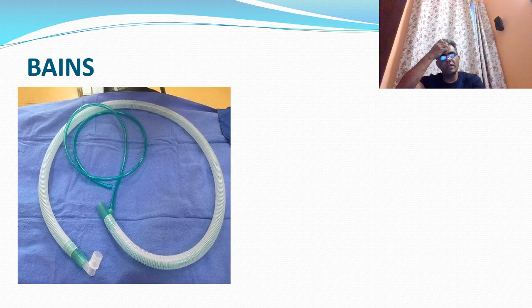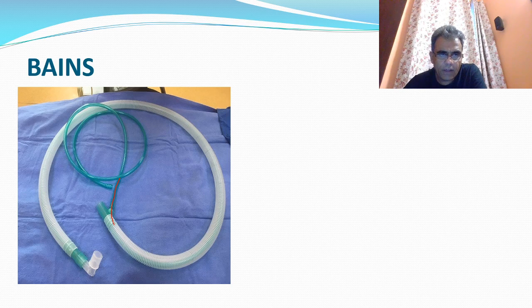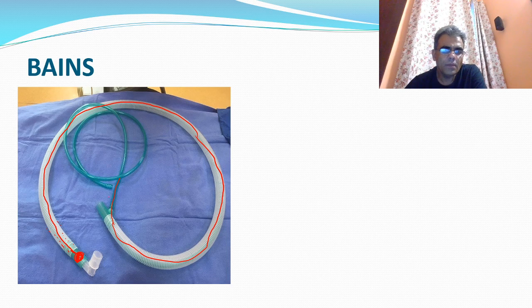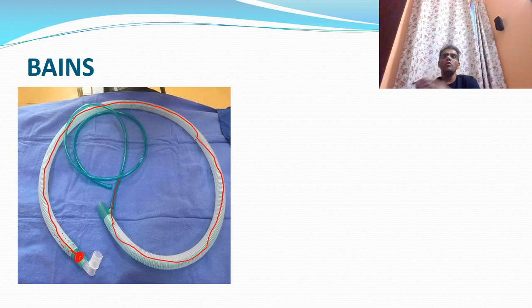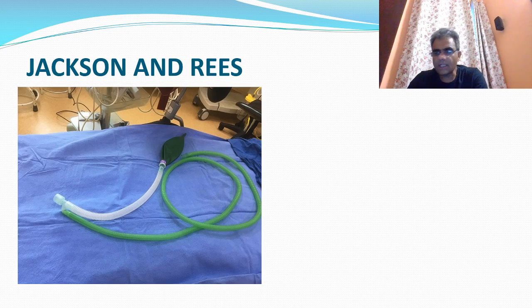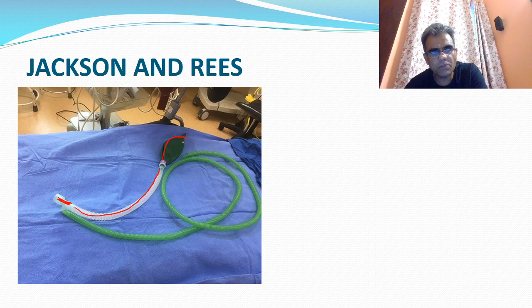Looking at the visual impression of these circuits: this is the Bain's circuit — you can see the inner tube going all the way through. They are made transparent so you can see if the two tubes get kinked. The point where mixing is possible is visible, and expired gases go through the outer tube. An advantage of Bain's circuit is its long length, making it useful for neurosurgical patients where the anesthetist stands far from the patient. This is the Jackson-Rees — originally just an Ayre's T-piece to which Ayre attached tubing, and then Jackson-Rees added a bag.